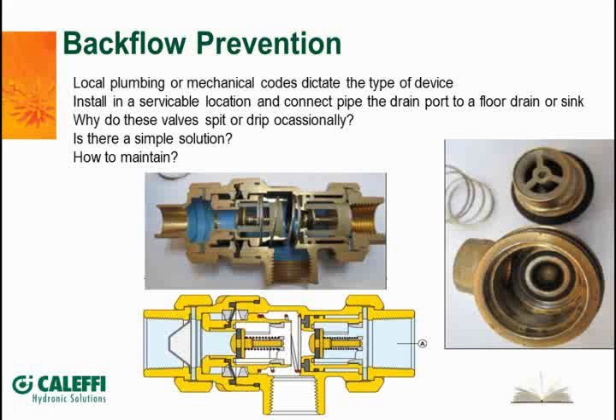Now, the other thing that can make these drip from time to time, and it can be an intermittent drip, and unless you're there when it happens, it's a tough troubleshooting call. But anything that could cause this little spool to jump or to move in here will cause this thing to spit a little bit of water. So if this spool, for some reason, just jumped off its seat for a second or two, this water that's coming through here now is going to have a path and access to go out the vent.